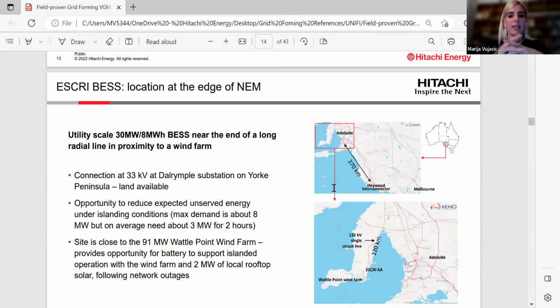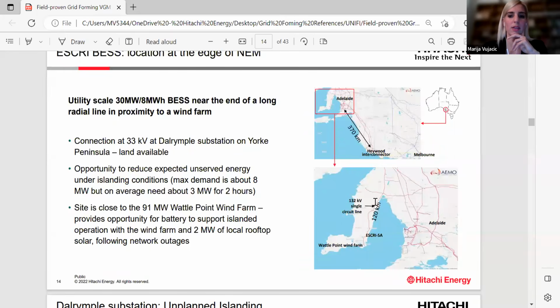So, a little bit more detail, and you can see here where the battery energy storage system is installed. It is installed at the end of this long single supply line in close proximity to a 90 megawatt wind farm. It is connected to the 33 kV network, and this area suffered quite frequent lightning strikes. So the requirement from the customer was that in case of a fault at the upstream network, the system needs to island and continue supplying the local loads, with seamless operation and integration with renewable energies, in this case the wind farm, as said before.